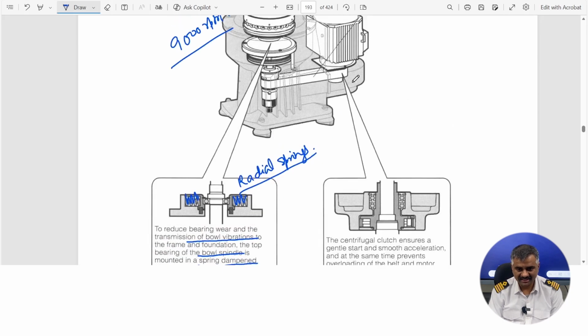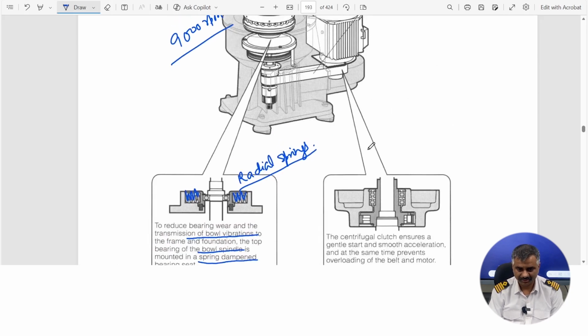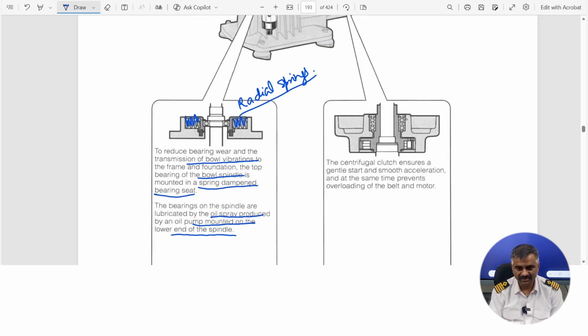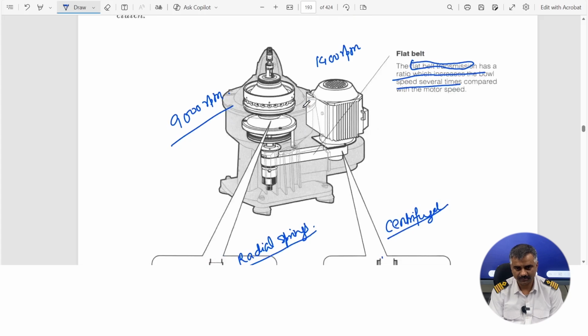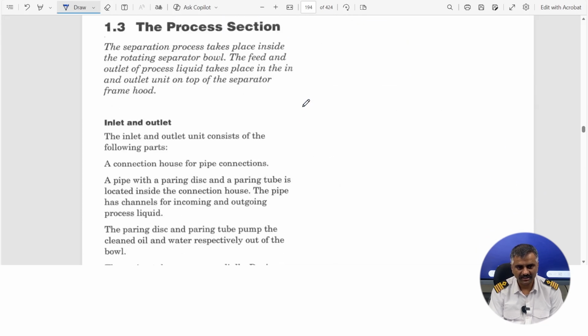On this end we have a centrifugal clutch. Why do we use a centrifugal clutch? A centrifugal clutch is basically the same as, or similar in arrangement to, friction pads. The purpose is to give the purifier a gentle or smooth acceleration, so the motor will not be overloaded while starting. It prevents the overloading of the belt and motor. That is why we are using a centrifugal clutch. Same as your Mitsubishi purifier mechanism, you have a centrifugal clutch there also.